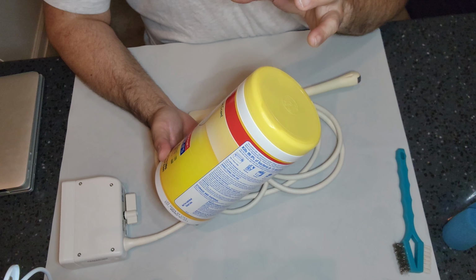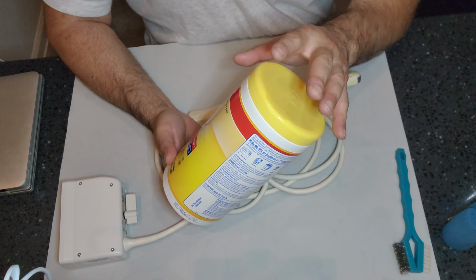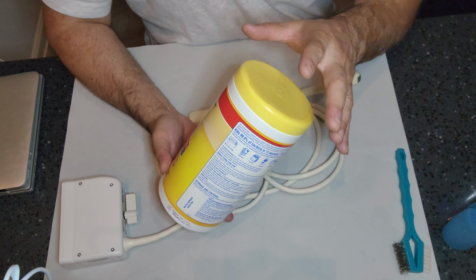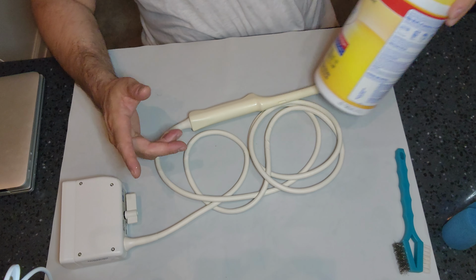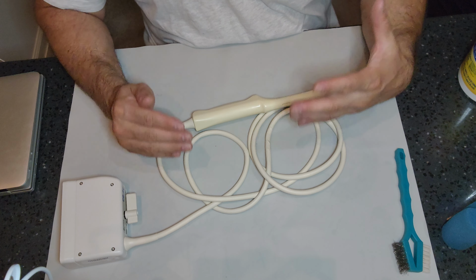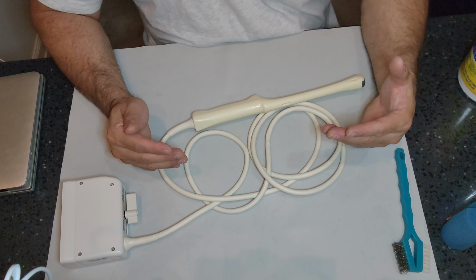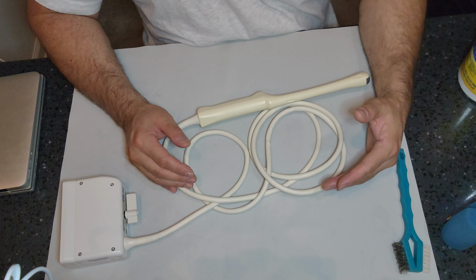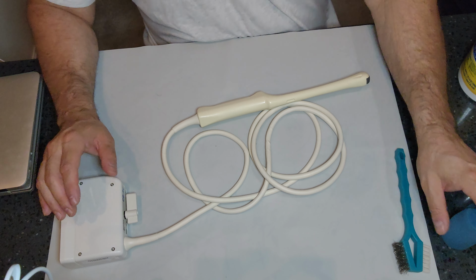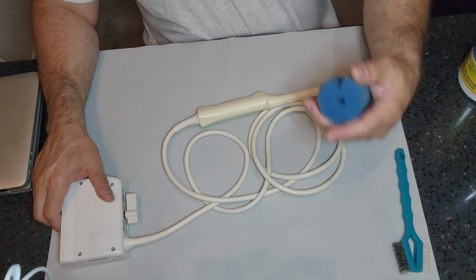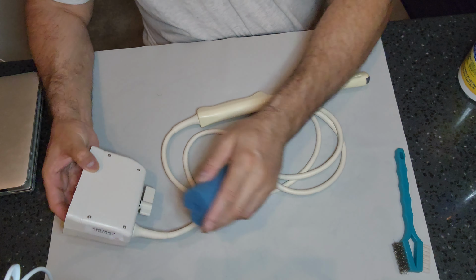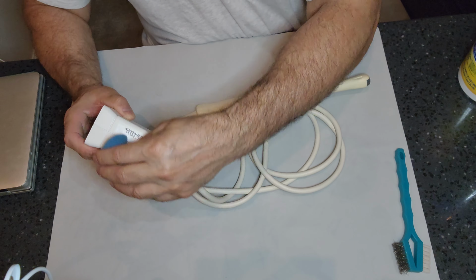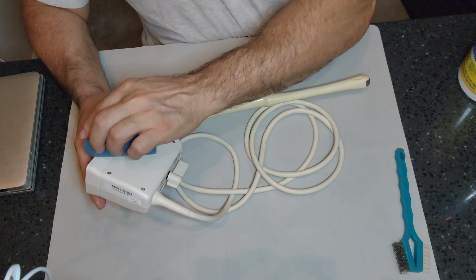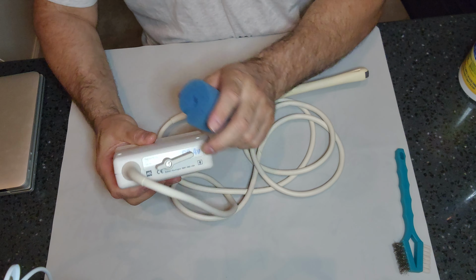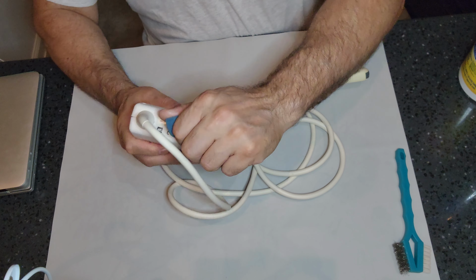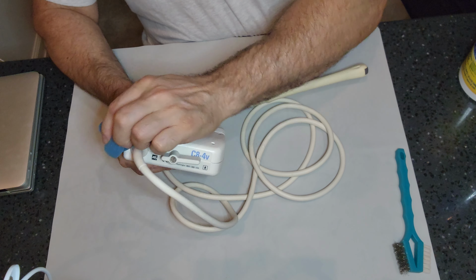Does it have that capability? Is it a cleaner and a disinfectant wipe? Can it be used for both applications? And again, the IFU of the probe lists so many options. So, again, check it out, see what it says. But if you can use a mild detergent, then you want to go ahead and grab a sponge or a towel, wipe the box off really good. Careful not to splash the connectors, so always on a downward angle away from you. Cleaning very good all around the box.